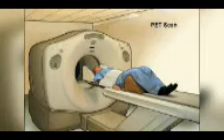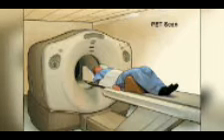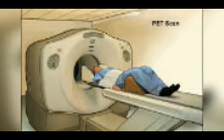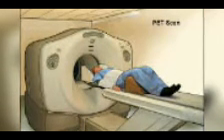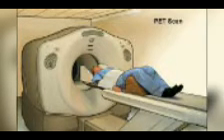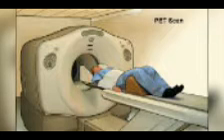During the scan, a record of tissue concentration is made as the tracer decays. As the radioisotope undergoes positron emission decay, also known as positive beta decay, it emits a positron, an antiparticle of the electron with opposite charge. The emitted positron travels in tissue for a short distance, typically less than 1 mm, but dependent on the isotope, during which time it loses kinetic energy, until it decelerates to a point where it can interact with an electron.